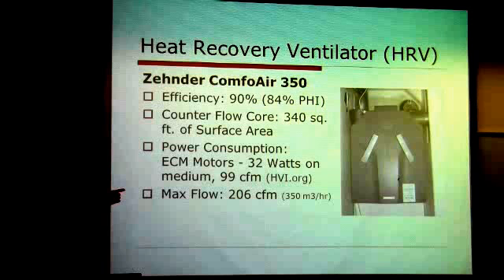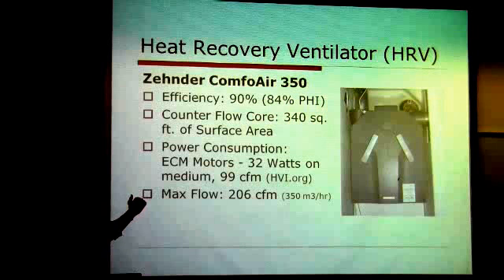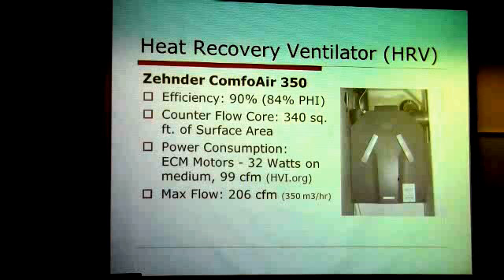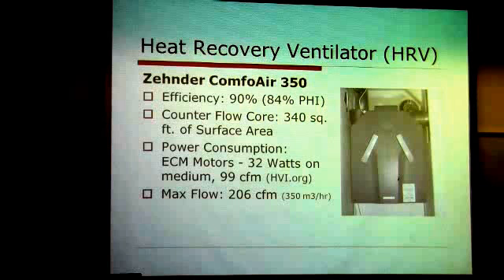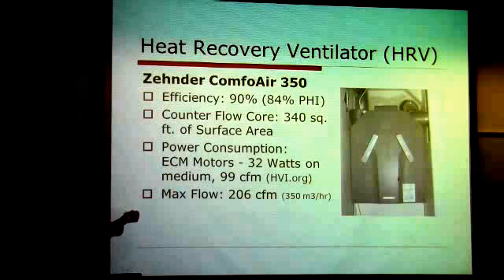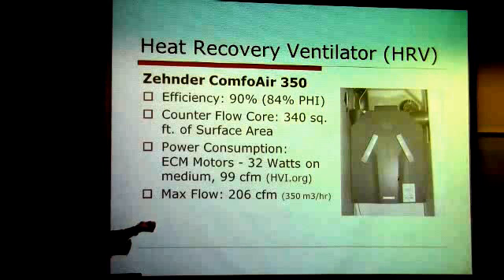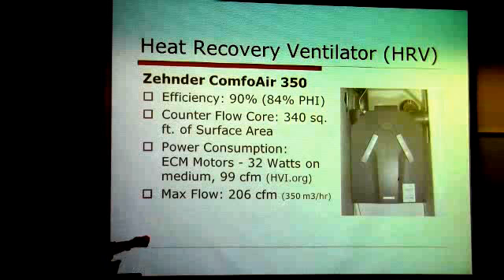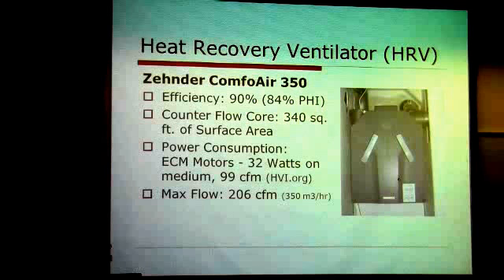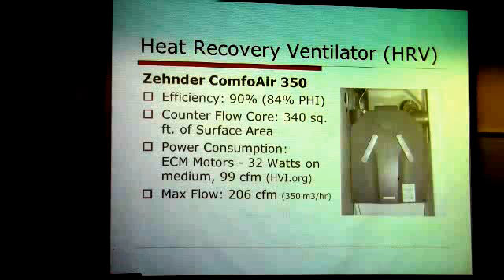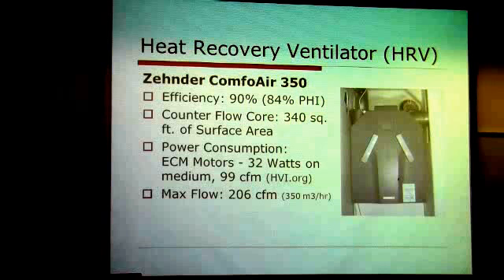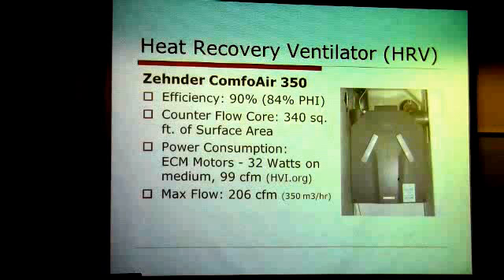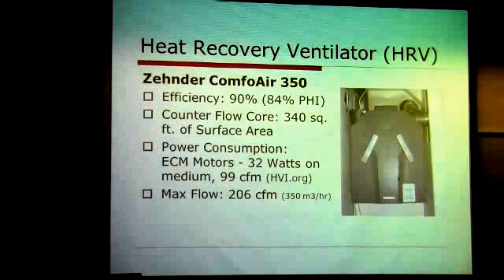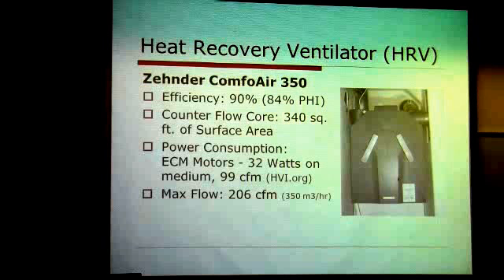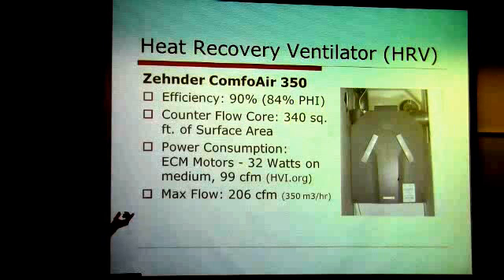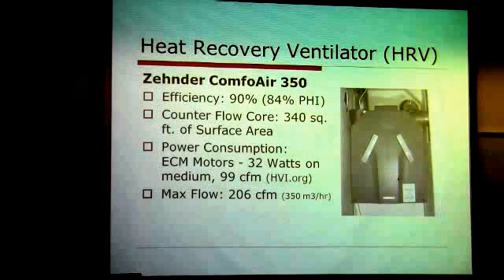However, if you get the air down to 60 degrees and the inside air is 75, you're only providing about 15 degrees delta of cooling, and these systems run about 60 to 100 CFM. So you're less than a kilowatt of cooling, maybe around 2,000 BTUs of cooling, which is negligible on a normal common house, but on a passive house that might be a third to half enough to cool it, or in our climate maybe that's enough to keep it cool. So there are some things, but it's tough to cool because you're dealing with such a low delta.